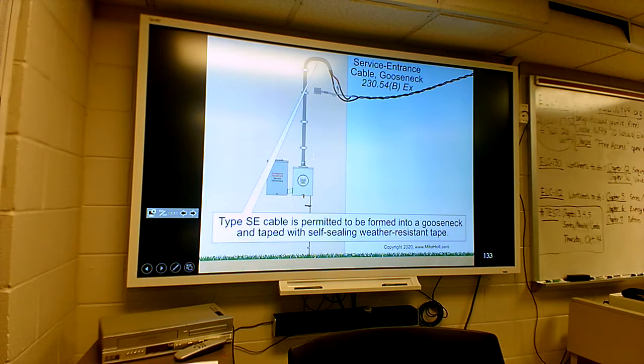And so here, they're actually showing a cable. This is not even in conduit. That's an SEU cable, service entrance cable. That's just cable that's coming out of their straps. And they've actually just got it bent over like a weatherhead, but it's not even a weatherhead. It's just the cable itself being bent. If it's rated for outdoor, you know. And then they taped it on the end, a self-sealing weather-resistant tape on the end of the cable where your conductors come out.